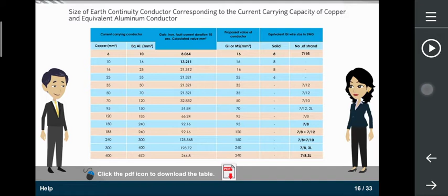So Mayank, how do we arrive at or determine these sizes? Good question. The following equation is used for determining the size of the earth bars and conductors. For riveted joints, A is equal to 0.0054 I root T. In this formula, A is the cross-sectional area in mm square, I is the amount of current flow through the earth wire in amps, and T is the duration of current flow in seconds.